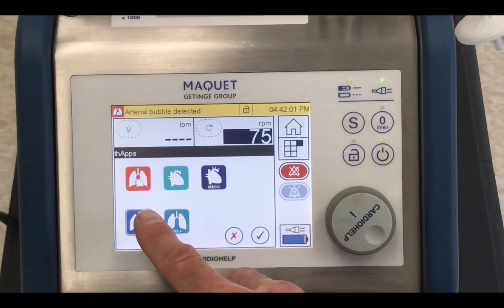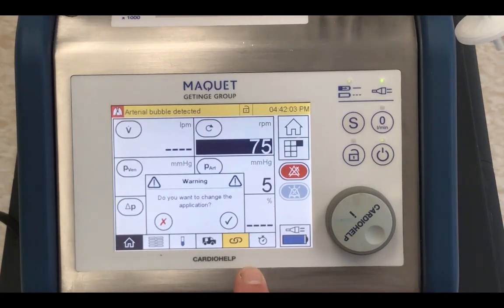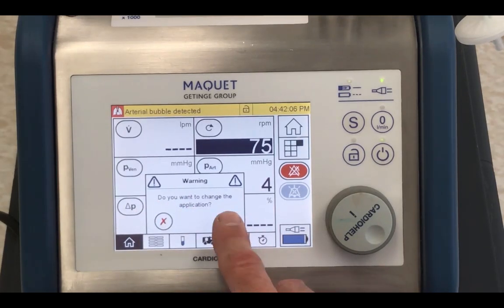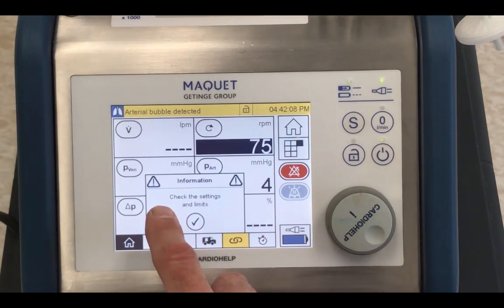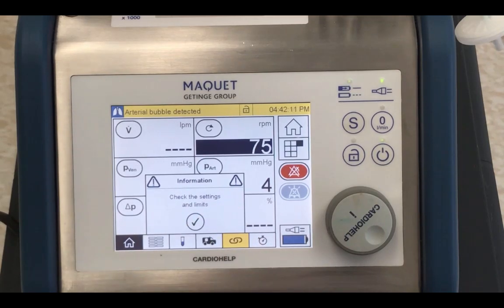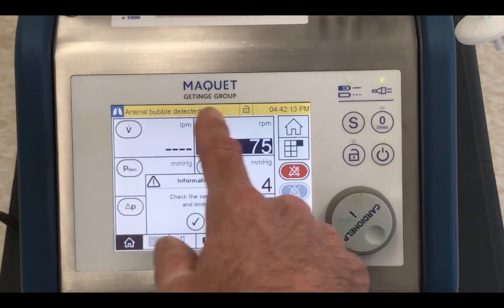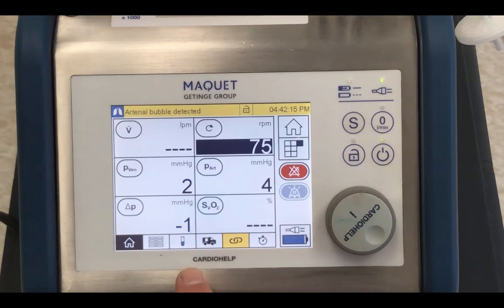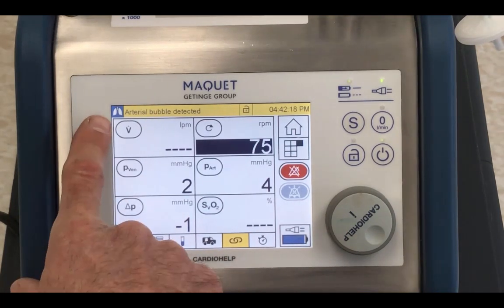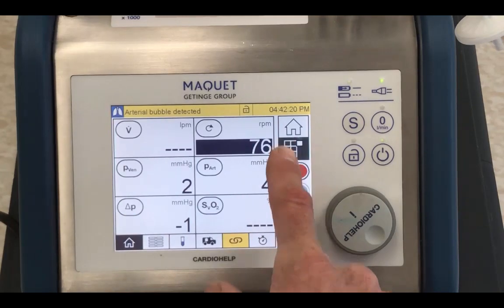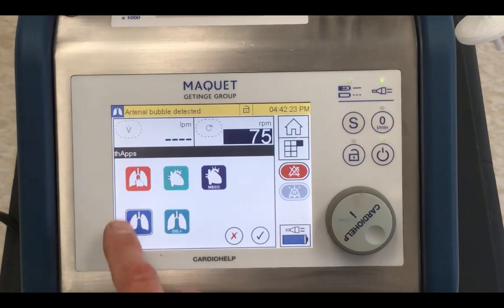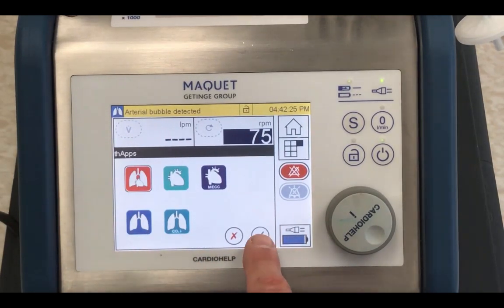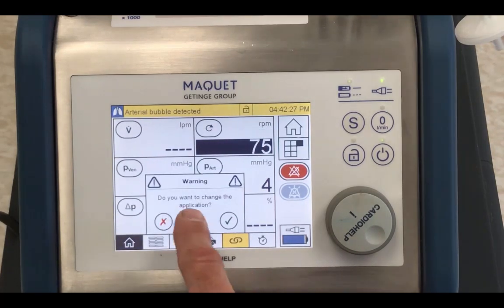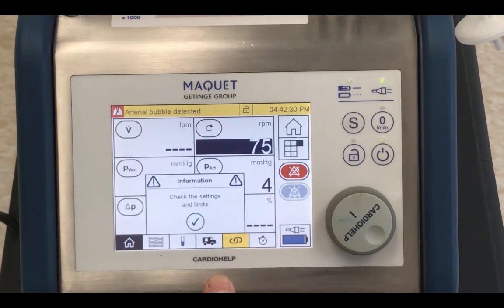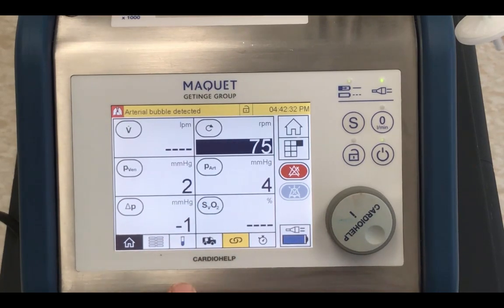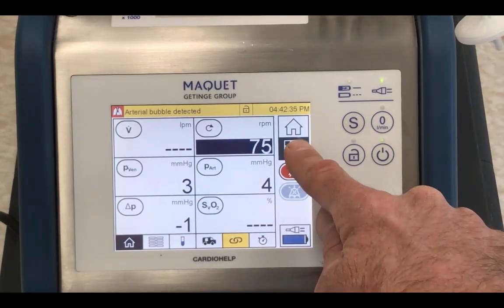The green button enters your selection. So now it'll enter the selection. It's going to ask, do you want to change the application? We're going to say, yes, we do. And it's going to say, then check the settings and limits, because if you just change your application, then maybe all the parameters you had previously set are not appropriate anymore. But you see now the icon is blue. Let's just change it back to red. Let's enter that selection with the green checkbox. Let's confirm that we intended to do that, and let's promise it that we will check our limits. Go back to our Tetris button.